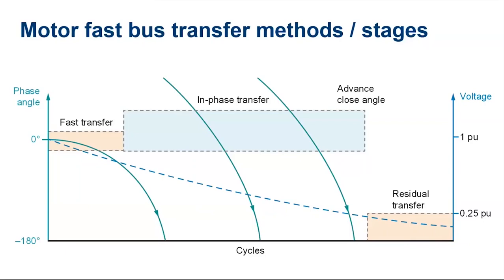In this one, the relay accurately measures the residual voltage, and it initiates the transfer when the motor bus voltage magnitude drops below the user-selected threshold. This is applicable for low inertia loads. Now, Marcos will walk us through the details of each of these transfer methods.